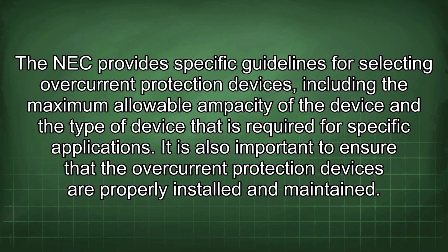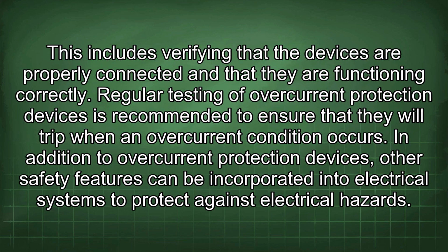It is also important to ensure that the overcurrent protection devices are properly installed and maintained. This includes verifying that the devices are properly connected and that they are functioning correctly. Regular testing of overcurrent protection devices is recommended to ensure that they will trip when an overcurrent condition occurs. In addition to overcurrent protection devices, other safety features can be incorporated into electrical systems to protect against electrical hazards.